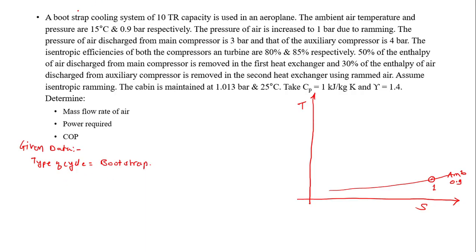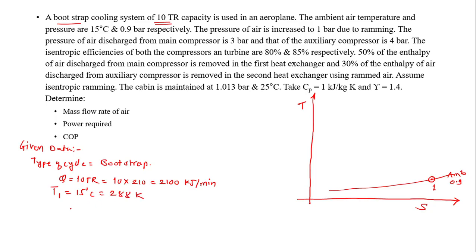The system has a cooling capacity of 10 TR, so Q equals 10 TR. Converting to kilojoules per minute, multiply by 210 to get 2100 kilojoules per minute. The ambient air temperature and pressure are given as 15 degrees and 0.9 bar, so temperature T1 is 15 degrees Celsius which is 288 Kelvin, and pressure P1 is 0.9 bar.